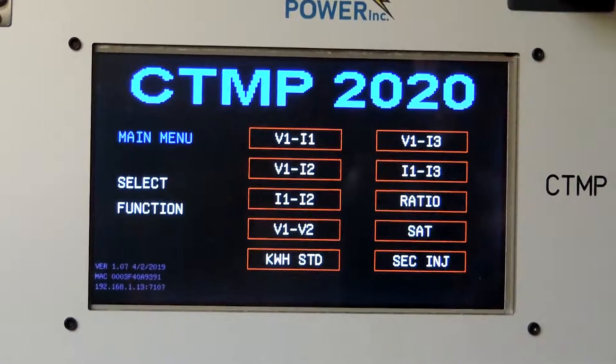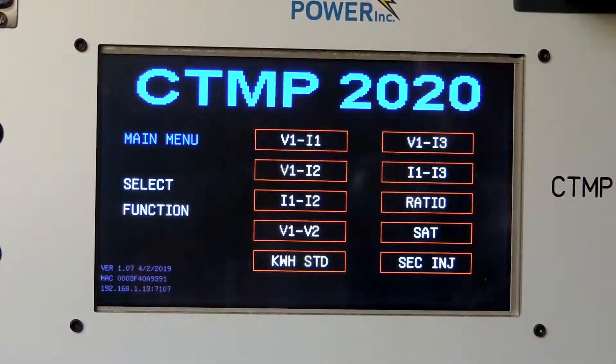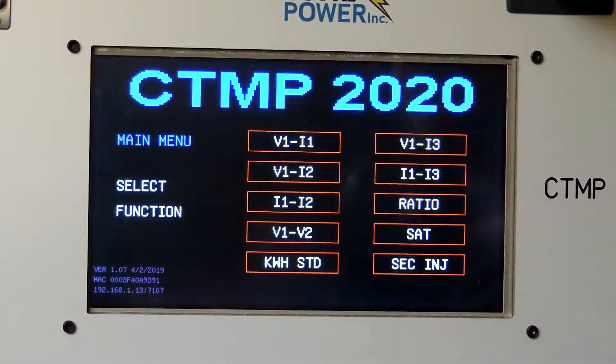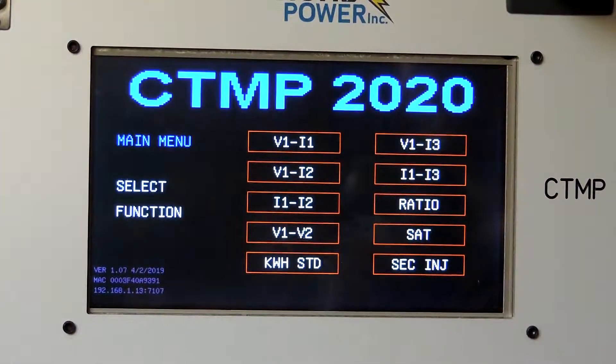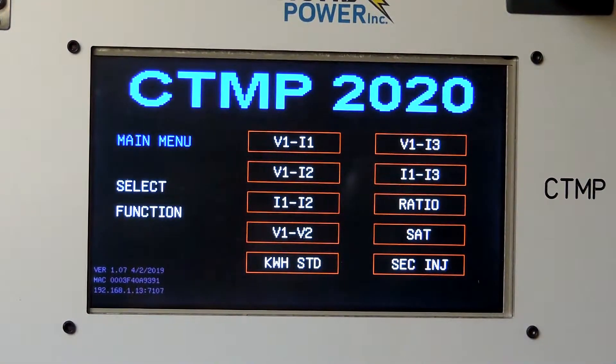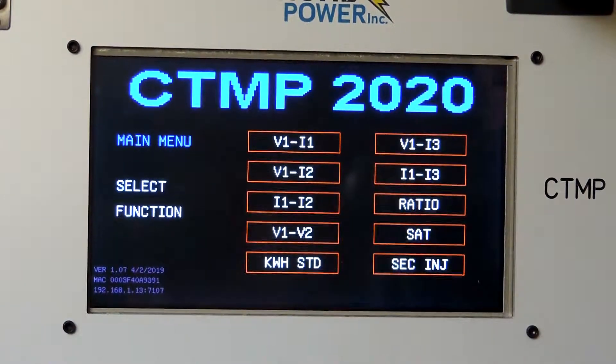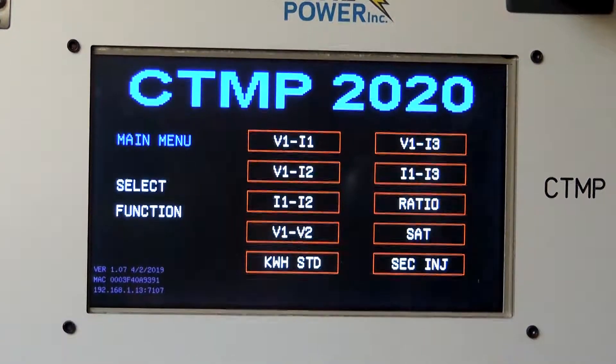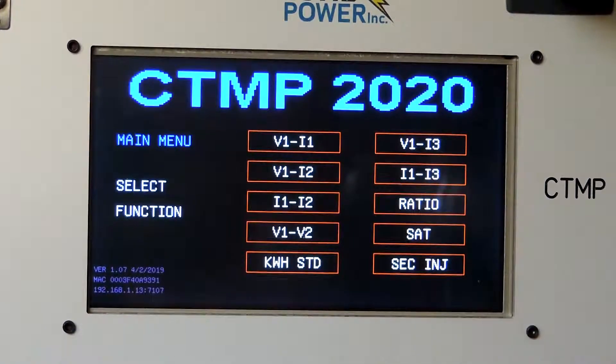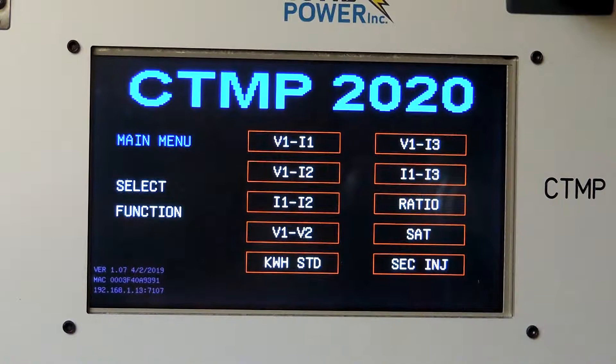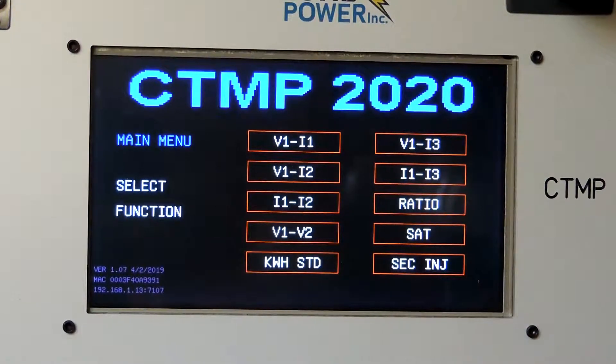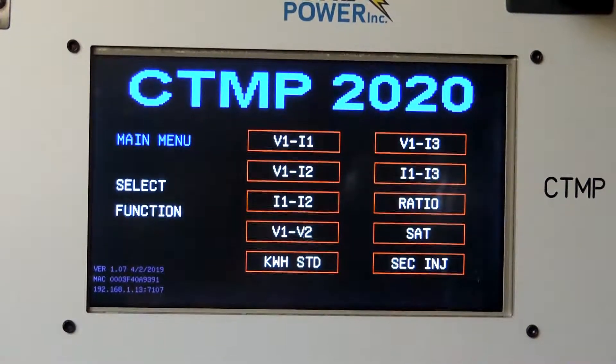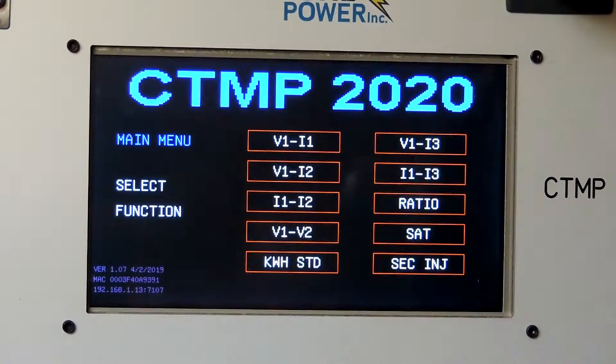Okay, this is going to be a little demo of testing a basic single tap CT. This happens to be a 2005, and we're just going to do a ratio, polarity, saturation test on it.